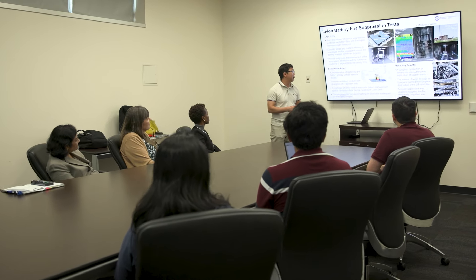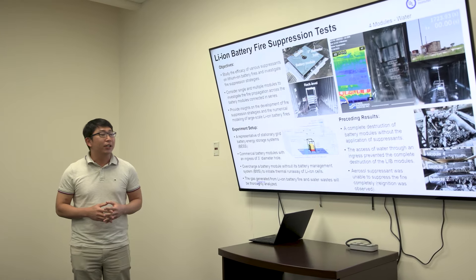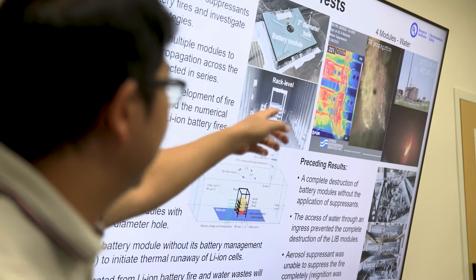Water has been used as a suppressant against lithium-ion battery fire because of its abundance and excellent cooling capability. On the other hand, aerosol can put out gas-phase combustion quickly. We also found that water could stop thermal runaway of lithium-ion battery modules with ingress through the three-inch diameter hole on the top cover.